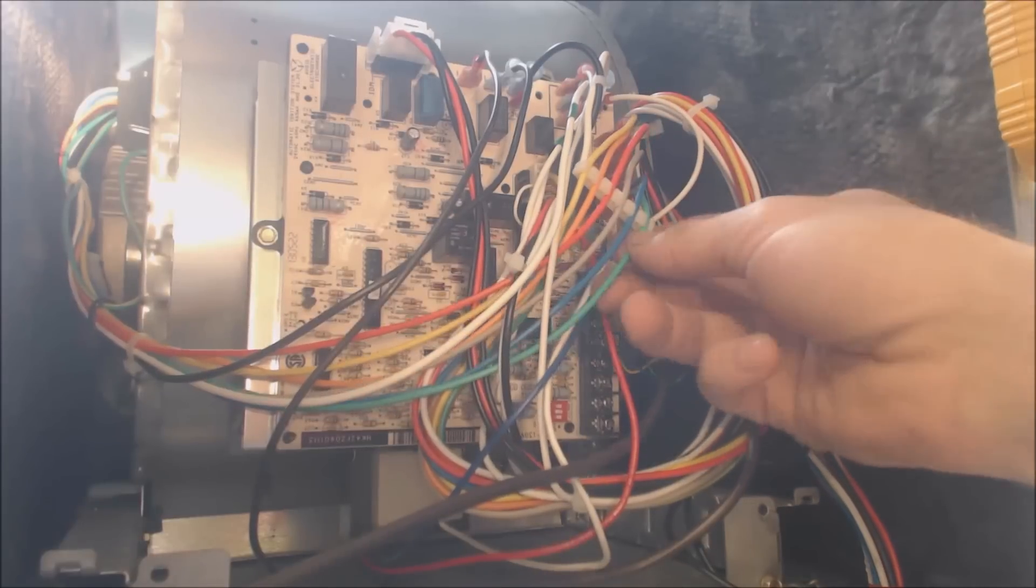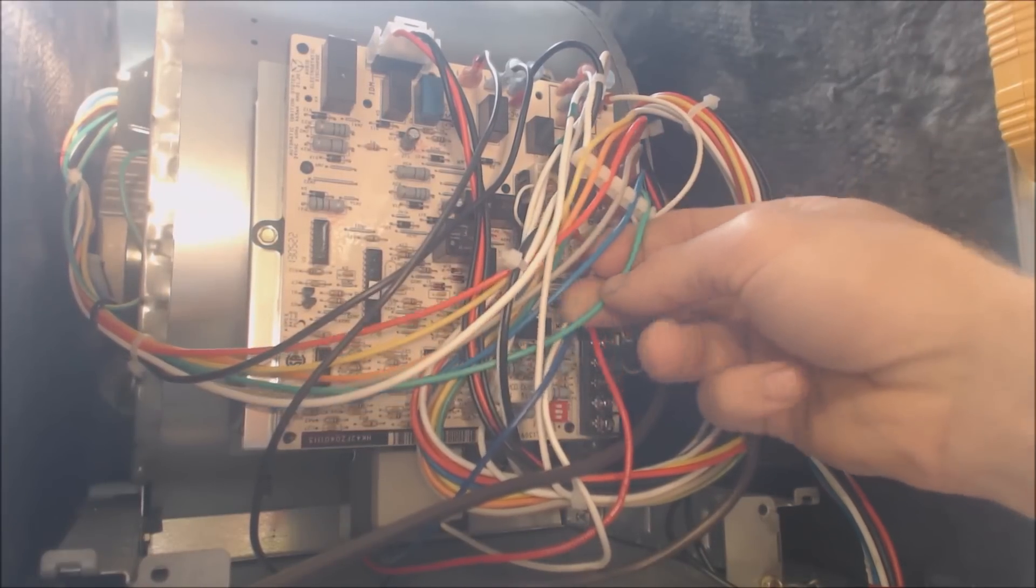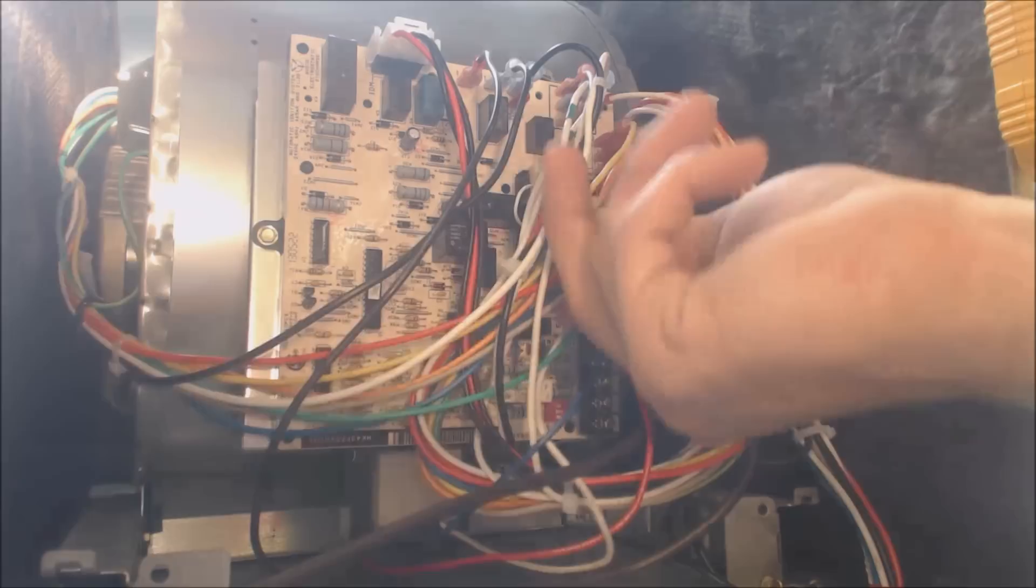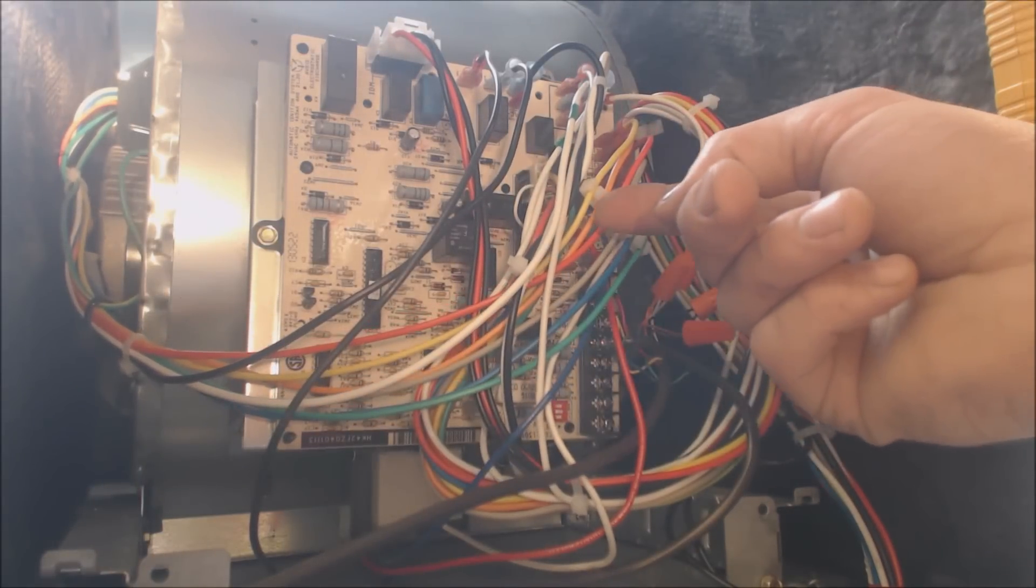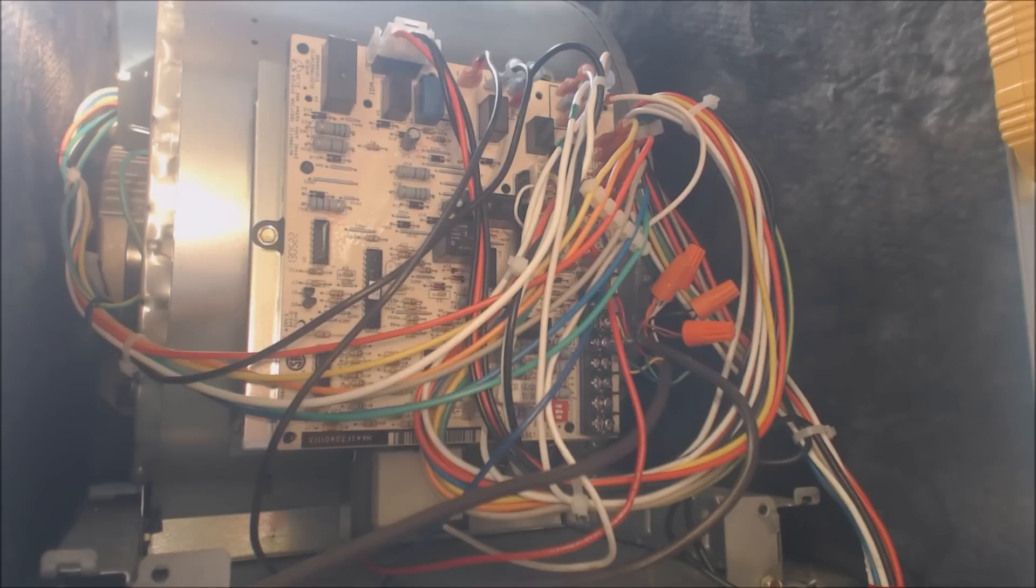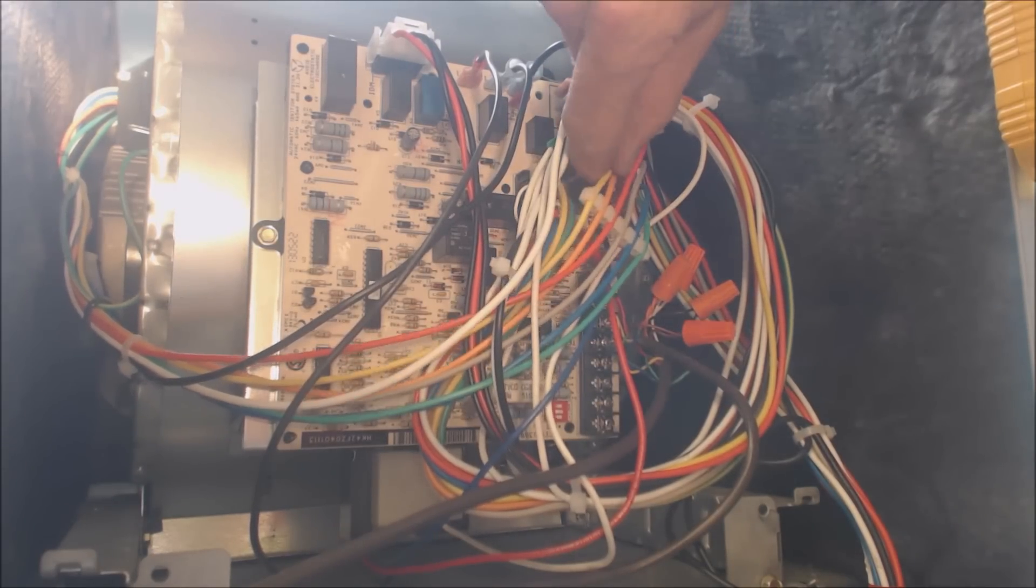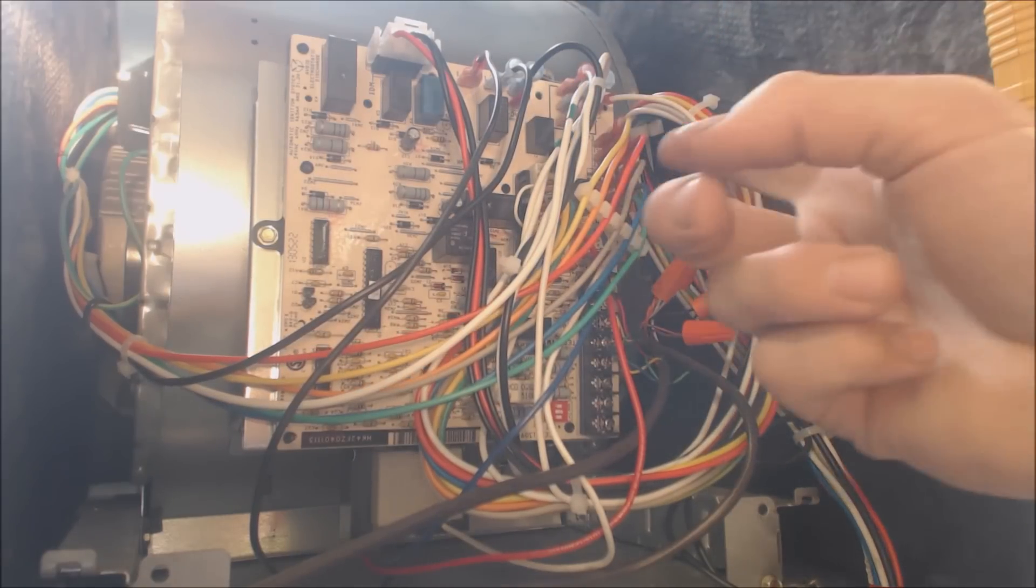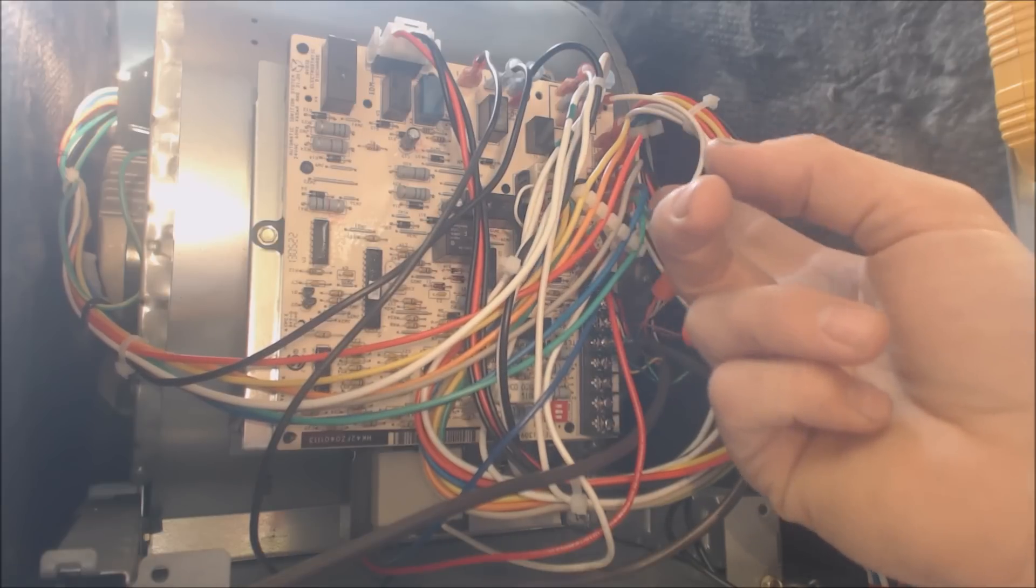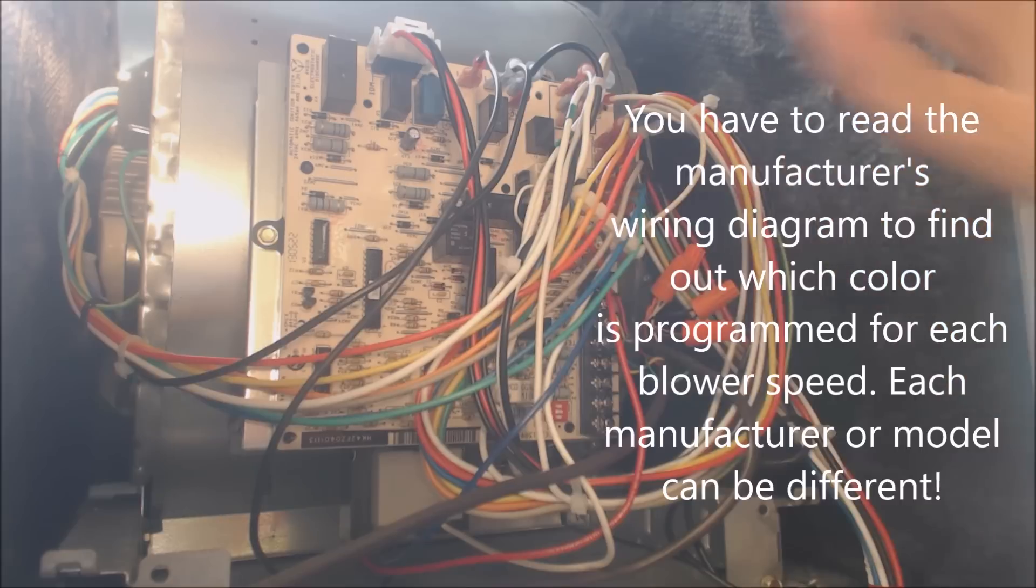Okay, so this right here is your common for all of your 24 volt wires. You have five speeds potentially right here. Blue, gray, red, orange, and yellow on this particular one. And for this manufacturer, they actually program that yellow and orange on the top are just spares and that they're not used. In this case, the red is the low heat, gray is the cool, and the blue is the high heat.